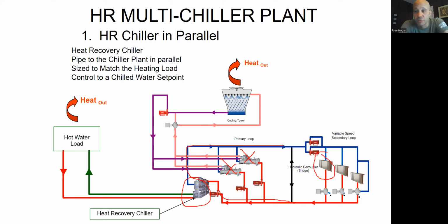If your building only needs chilled water in the summer and you only need hot water in the winter and you don't have any overlap, then fine, you don't really need this. Or if you only have one or two months of overlap in the spring, you don't need this. But if you have year-round need for hot water, for example, that building I mentioned where the interior zone needs cooling all the time, and then you have boilers that are, maybe it's a hotel or something, and you got boilers that are doing water for showers and laundry and all that. You need hot water all the time. Or maybe it's a high school, right? And you need chilled water to cool certain areas. And then you have the swimming pool that needs heat all the time. These kinds of things where you have a lot of hours of overlapping heating and cooling needs. That's where this heat reclaim chiller would come into play.